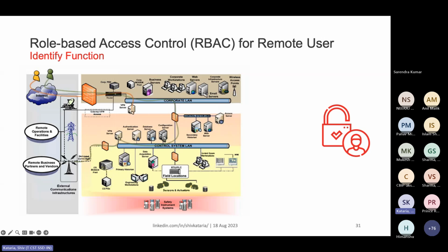say substation or your control center. So if you give direct access using TeamViewer, then you basically are giving direct access to this particular area of your control system. And that is not a secure method. If anything goes wrong, there would be no accountability. There would not be a mitigation measure for the user. And it will become difficult for us to troubleshoot that particular system.